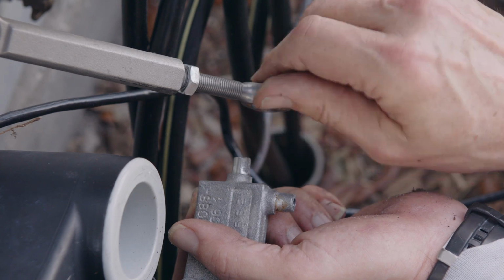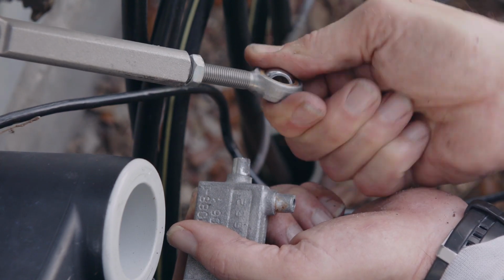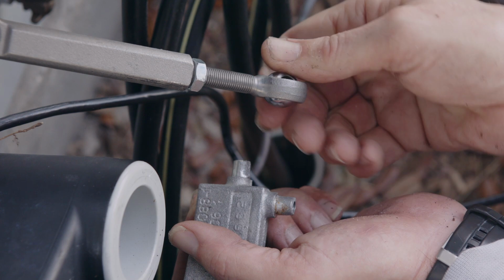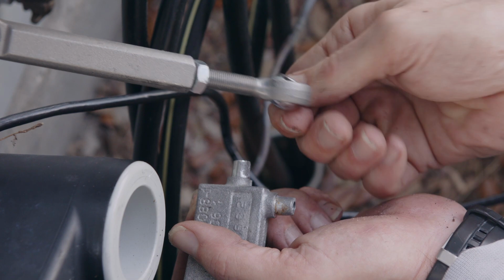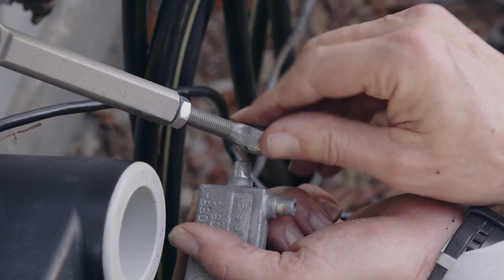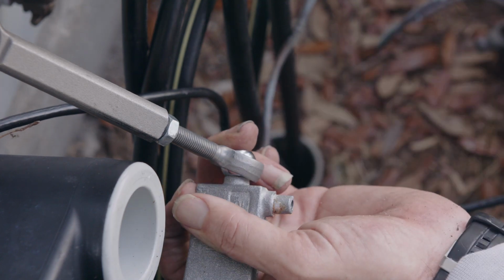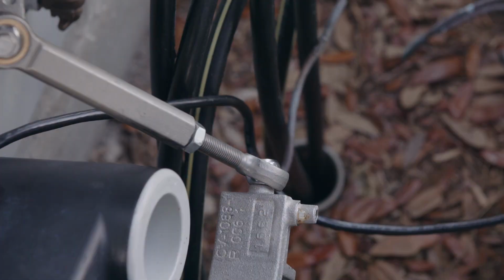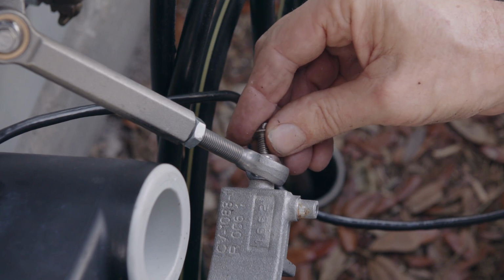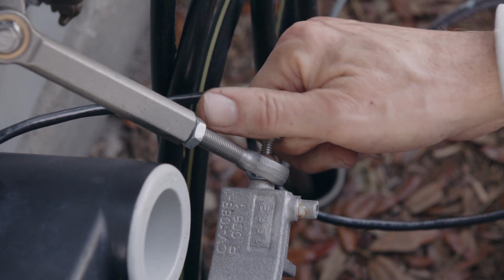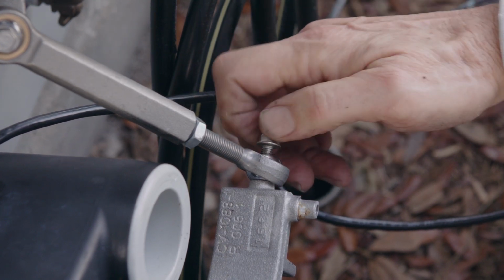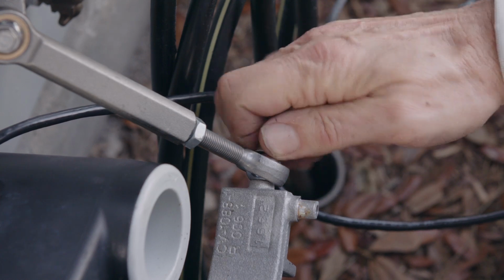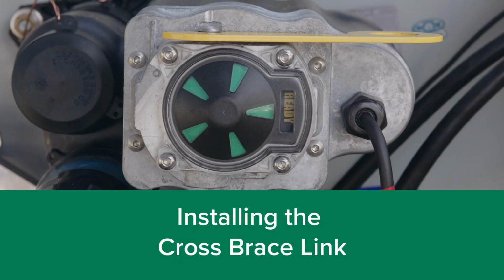Step 2. Reduce the length of the link by 1/8 inch by turning the end in 2 full turns clockwise, 360 degrees by 2, to support the weight of the bushing well interrupter. Step 3. Lift the H1A bushing well interrupter until the ball joint slips onto the boss. Step 4. Connect the adjustable link to the boss using a 1/4 inch by 20 flange head bolt. Hand tighten.